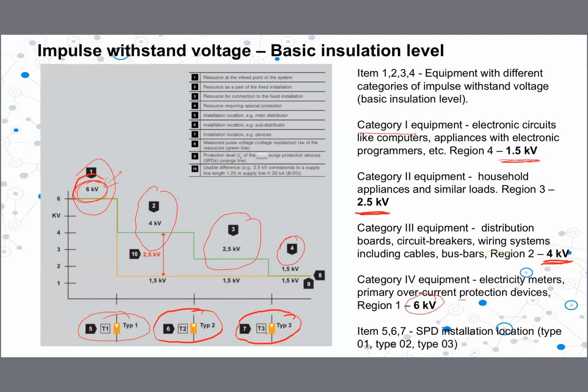Therefore, the voltage level value of the surge protection device, that means UP, should be less than 6 kilovolt in this type of surge protection device. Type 2 should be less than 1.5, right? Because if it goes more than this, it can be harmful. And type 3 also 1.5. If it goes more than that, it will damage the insulation of the equipment, right? So that's how you select the insulation level of the surge protection device.